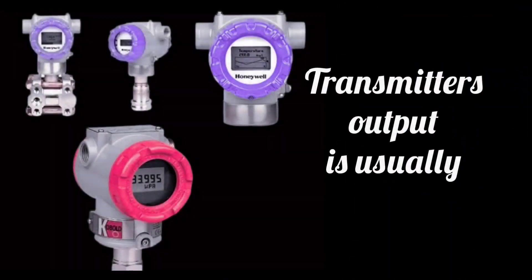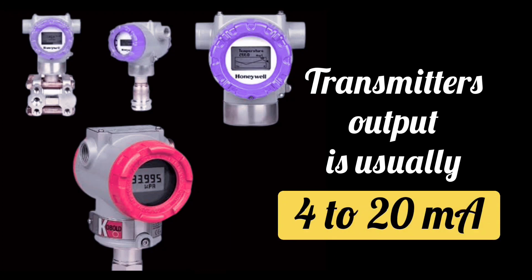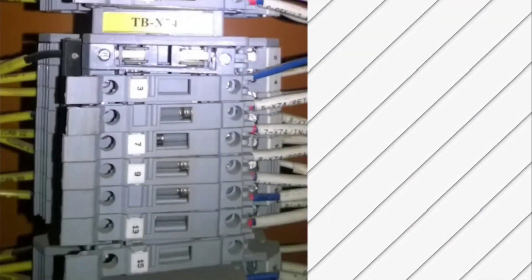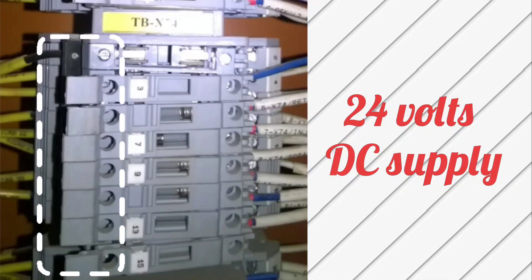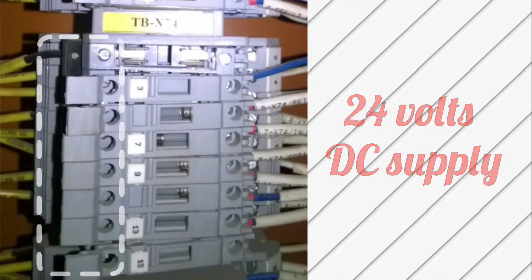The output of transmitters is usually 4 to 20 milliampere. There is a type of TB for transmitters in PLC panel. For 24 volts supply, a strip will appear. Positive for all transmitters will connect from its front terminal only.